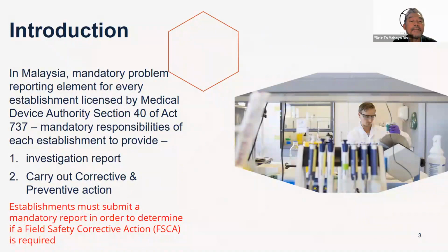I'm going to talk from the context of Malaysia. We have the Medical Device Authority, and the act which governs it is the Medical Device Act 737, which states the mandatory responsibility of each establishment. That means the manufacturer must provide an investigation report and carry out corrective or preventive action, and basically the establishment must submit a mandatory report in order to determine whether an FSCA, a field safety corrective action, is required.